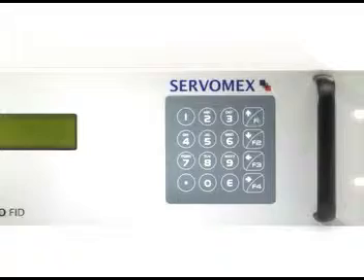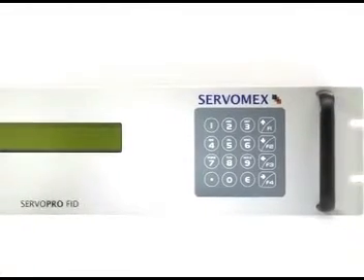Because the flame ionization detector uses a flame to measure the hydrocarbons, there are things sometimes that could go wrong in the process, or a very quick pressure swing that will shut off the flame. So in those cases, there's no more measurement coming from the analyzer. With the built-in flame sensor and the built-in electronic pressure regulator, we're able to detect when the flame goes off and to automatically reignite the flame.